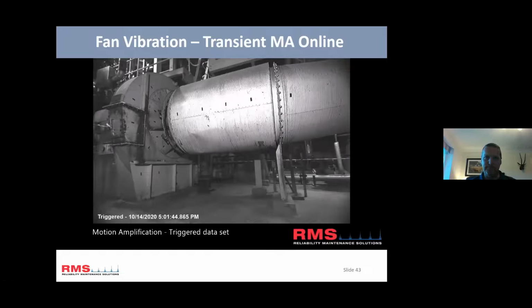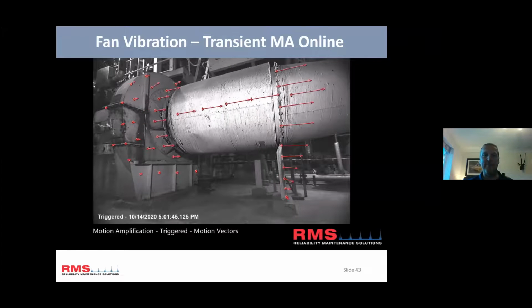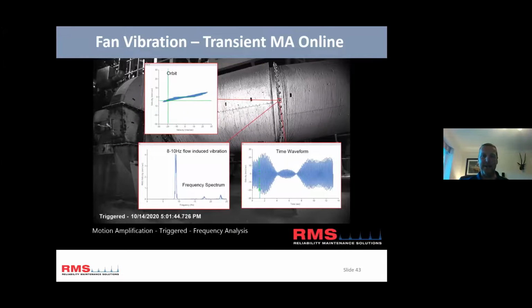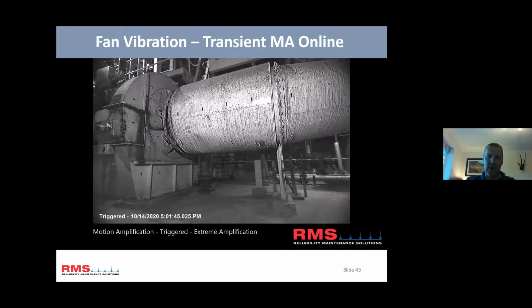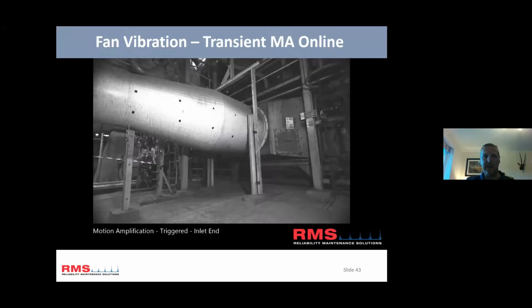Basically it was the suction side of the fan. There was a lot of motion, and it occurred when we looked at the process data, when the boiler was throttled down. Obviously the airflow was reduced into the fan, and this caused this axial motion on the suction side of the fan. What was happening is the casing was actually touching the fan impeller, which was unbelievable. So they're on a project now to isolate this and change the design, so that when this low flow occurs, it doesn't transmit the vibration into the fan itself. It was a great example of using the system online.